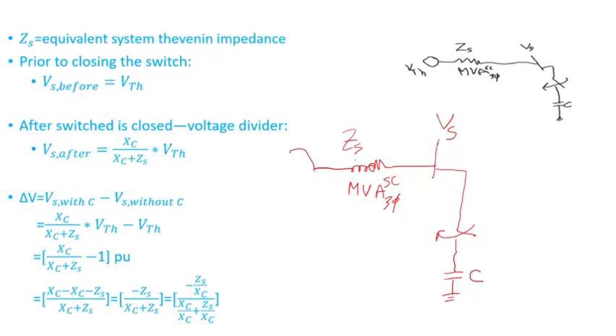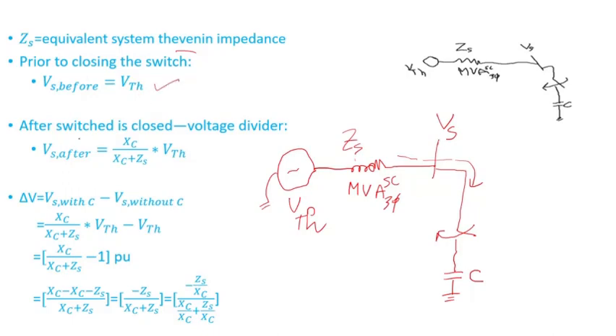The rest of the system we'll just write as the Thevenin equivalent — basically some voltage V-Thevenin. Keep in mind there are lots of things connected, so we just wrote the Thevenin equivalent of the system, where ZS is the equivalent Thevenin impedance. Prior to closing the switch, since no current will flow through the capacitor bank, VS is the same as V-Thevenin.